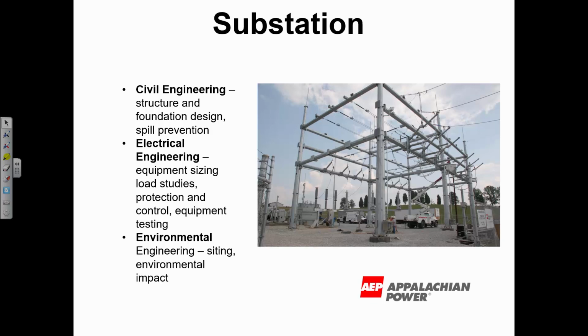Electrical, I want to talk a little about protection and control. How many of you are electrical? Okay, good. Protection and control is about the fuses and breakers that protect major pieces of equipment. If there's a fault out on a line, we want the breaker to operate before it damages that transformer, because the transformer costs millions of dollars and you don't want it to burn down because the breaker didn't trip. You have to make sure there's enough fault current at the end of the facility to trip that breaker.